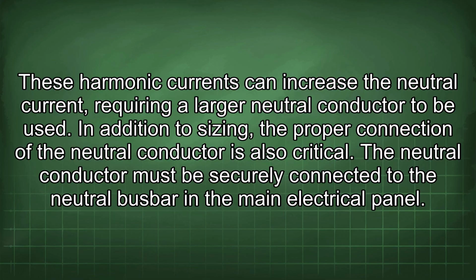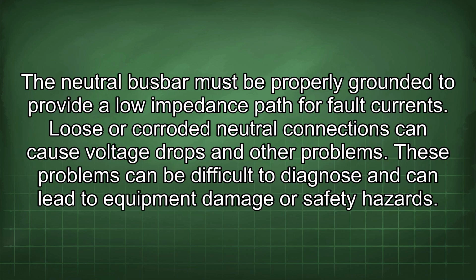In addition to sizing, the proper connection of the neutral conductor is also critical. The neutral conductor must be securely connected to the neutral busbar in the main electrical panel. The neutral busbar must be properly grounded to provide a low impedance path for fault currents. Loose or corroded neutral connections can cause voltage drops and other problems. These problems can be difficult to diagnose and can lead to equipment damage or safety hazards.